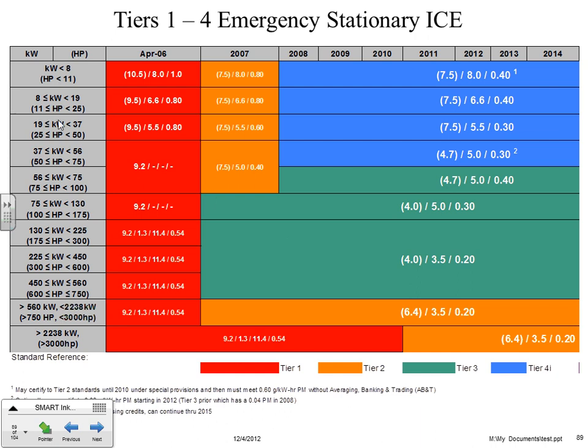Over here, they've got the horsepower sizes of the engine, basically. KW is not electrical KW here. This is mechanical to equate with horsepower on this side of the chart. And these are the compliance dates and the emission levels; back here was Tier 1, for instance. 2007 brought in Tier 2 for this size right here. And notice that some of the bigger ones are Tier 2 even today. So the horsepower of the engine will determine what tier level it's in. But we're basically here, 2012, and we're in compliance with all of our product line right now for emergency. There's no issues all the way through the end of 2014.